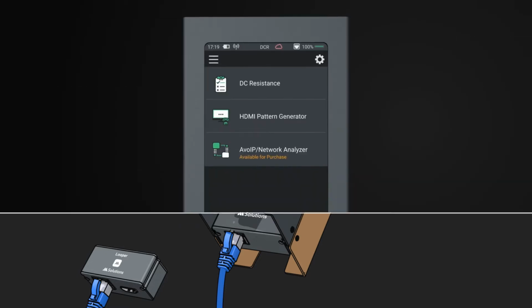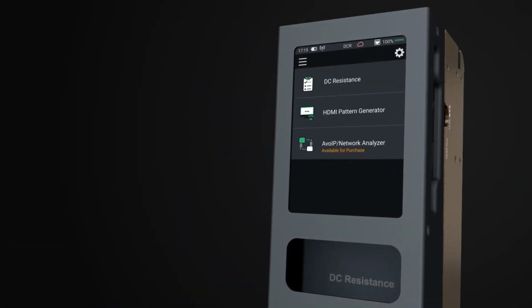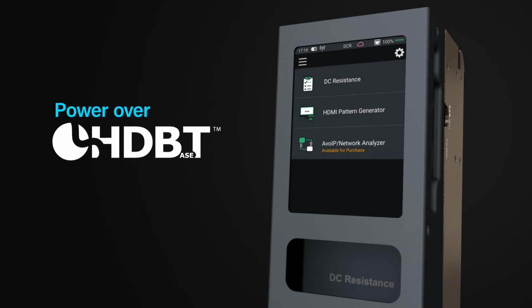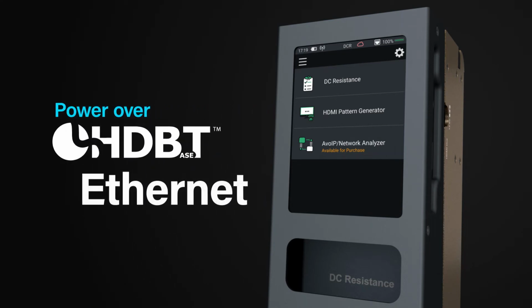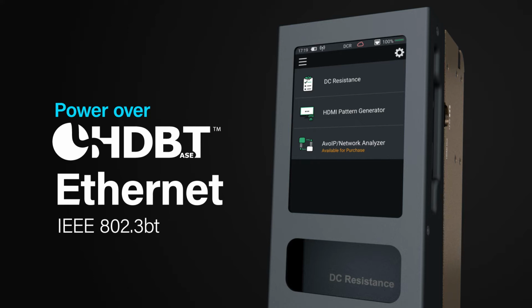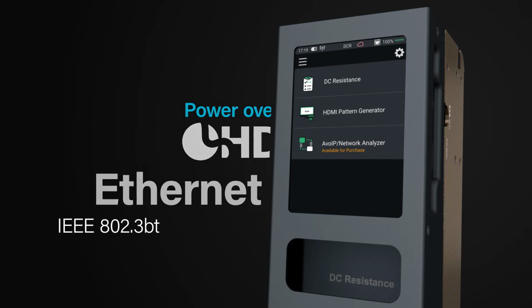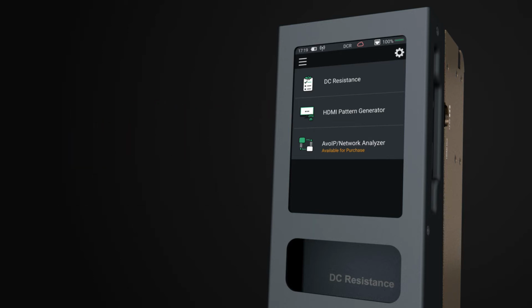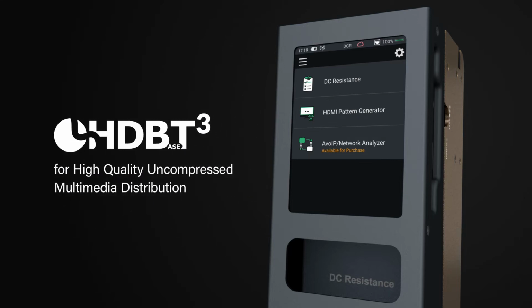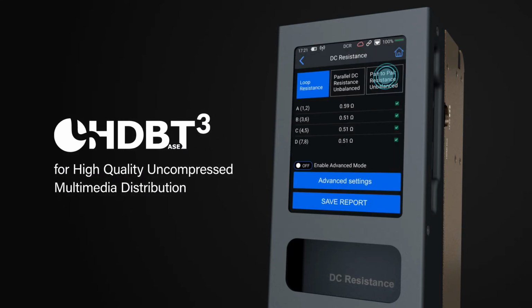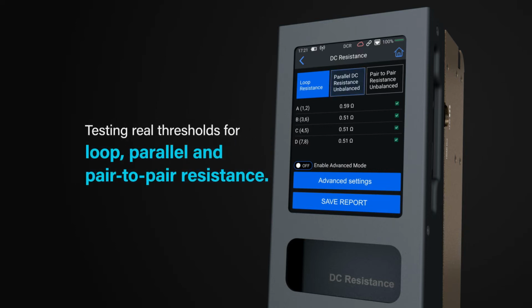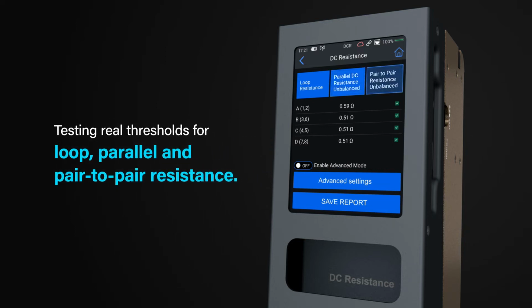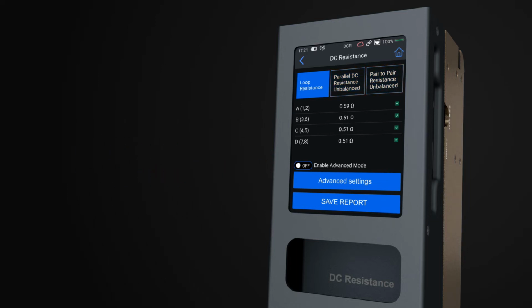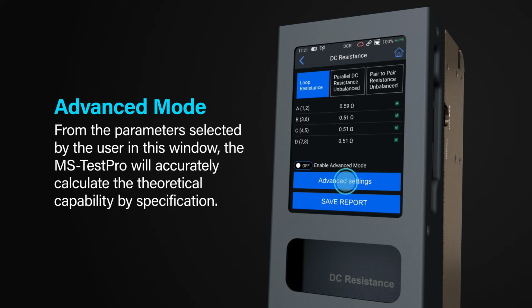You are now ready to qualify your CAT cable for its ability to send power over HD-Base-T or power over Ethernet to the IEEE 802.3 BT standard, or if testing your cable for use with the HD-Base-T Spec 3. The tests look at the quality of the cable with real threshold loop, parallel and pair-to-pair resistance. This can be drilled down with far more accuracy when setting the parameters in the advanced mode.